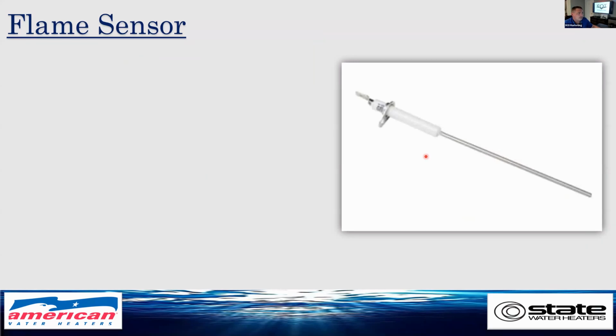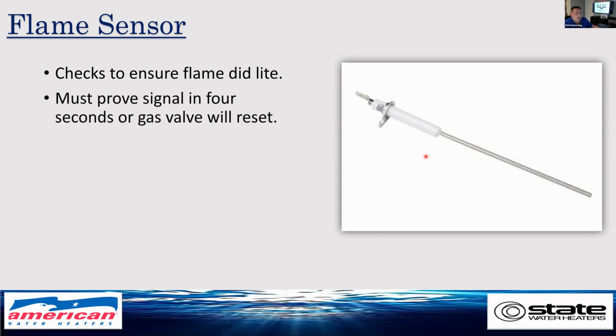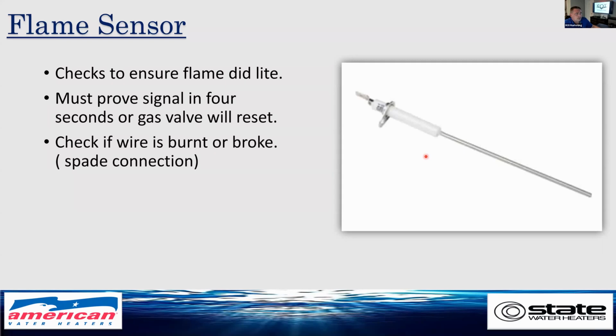Flame sensor. All the flame sensor does is check to ensure the flame did light. It must prove signal in 4 seconds or the gas valve will reset itself. Check to see if the wire is burnt or broken. And there's a spade connection on the outside of the unit leading up to the gas valve for replacement. A lot of times that spade connection is a failure point from somebody accidentally kicking the wire, carrying it the wrong way.